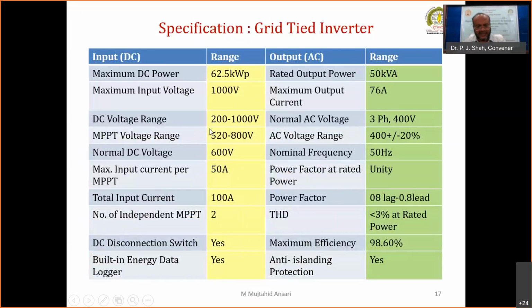Now, grid-tied inverters. While selecting grid-tied inverters, there are some parameters to be observed. What is the maximum DC power that can be connected, and what is the rated power output? Here the maximum DC power is 62.5 kilowatt, whereas the rated output power is 50 kVA. The output power is AC, whereas the input power is DC. So to get the proper voltage and proper output power, it is necessary to connect the number of modules in such a way that up to 90% DC is connected on the input side. So you may connect 55 kilowatt of DC PV modules, then it will give the proper output.